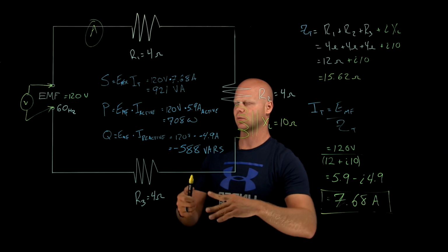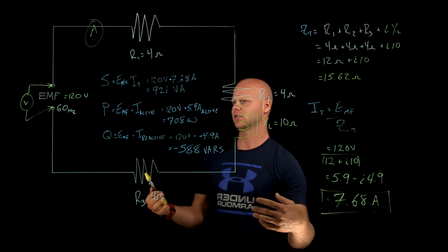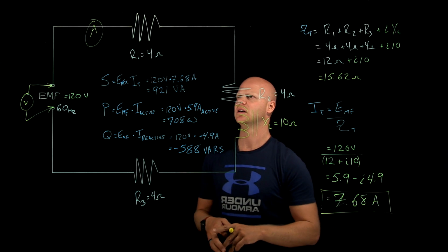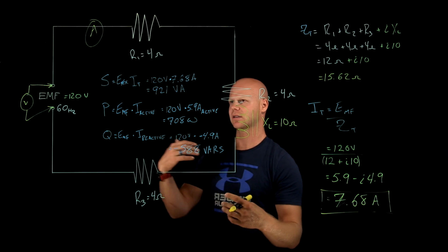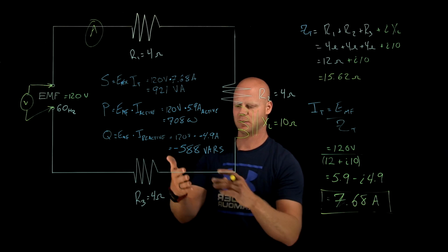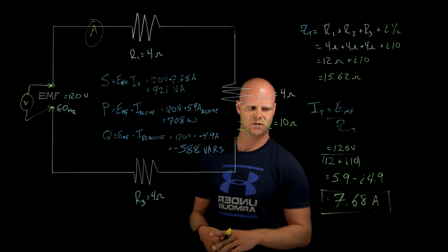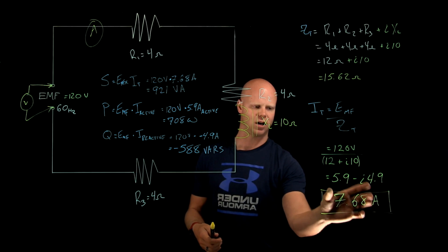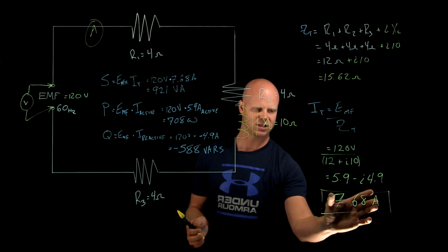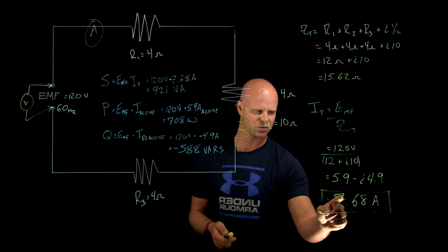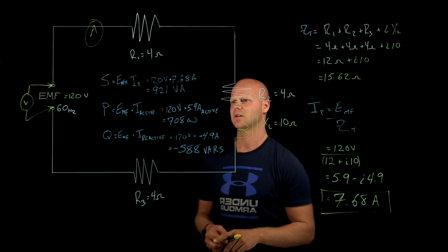When engineers are determining conductors and their allowable ampacity, they are looking at absolutely everything else. But when we're worried about sizing that conductor in the field and ask whether I need a number 10, a number 12, or a 750 kcmil, all of those calculations are done for us. It's based on that total, the thing I could walk up and measure, which would be that 7.68 amps.